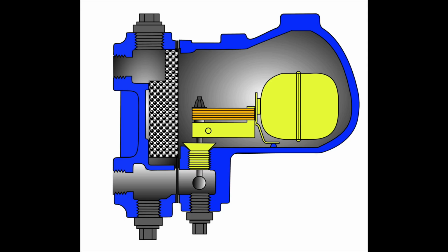That's why we want to have a float and thermostatic trap installed on unit heaters, not because you're going from 100% to 10%, but when that fan turns on, you're going from 10% to 100%. So if you don't have a trap that is a continuous, immediately open type trap, you might back up condensate, cause water hammer, damage the coils. So I recommend float and thermostatic traps on unit heaters.